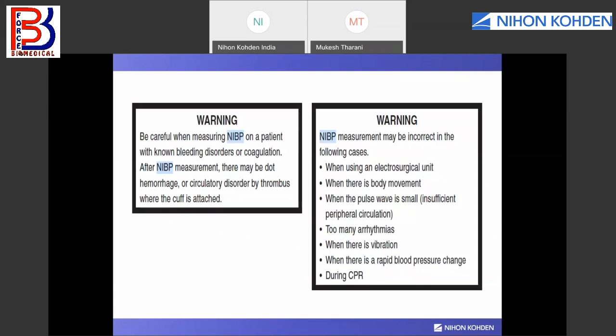There may be incorrect NIBP measurement because of the following reasons. Either an electrosurgical unit is being used nearby, or there could be body movement of the patient, or a very small pulse that cannot be detected through the oscillometric technique, or arrhythmias, or vibration on the bed, or a rapid change in the pressure, or maybe during CPR, the NIBP measurement could be incorrect. So if the patient is in an ambulance, the patient bed should be stable. And if the patient is in ICU, the patient should not be moving when the NIBP measurement is taken through the oscillometric technique.